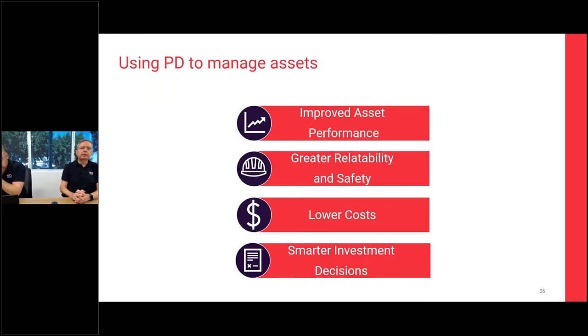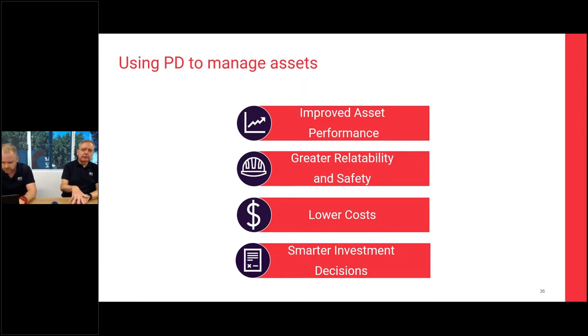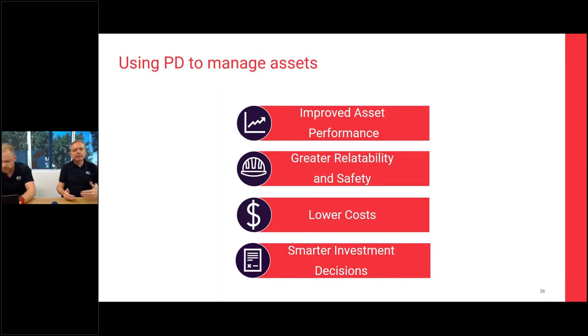Overall, we can get improved asset performance, greater reliability, and safety. We can lower costs — as stated at the beginning, we can generally save a third of the cost by proactively replacing cable joints that are discharging before allowing them to fail. One other big thing is that we've got aging networks in a lot of places. By doing widespread testing — and you can test a lot of cables in a relatively short amount of time if you can get access to the earth screens — you get an overall view of the condition of that network. That allows you to understand what may need replacement in the next five-year period and start making smarter investment decisions based on condition, in an asset area where we typically have less condition information compared to other asset groups.